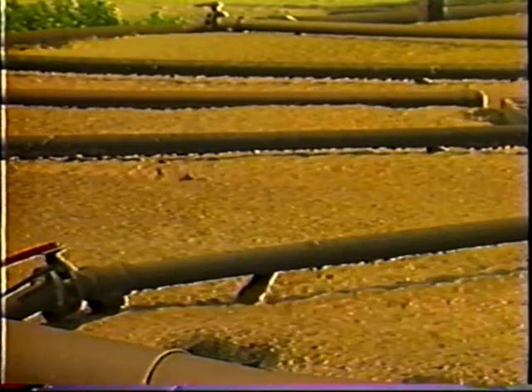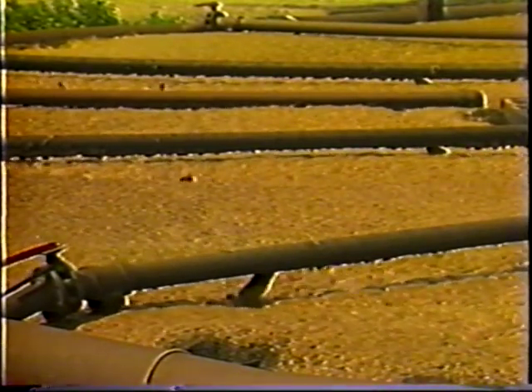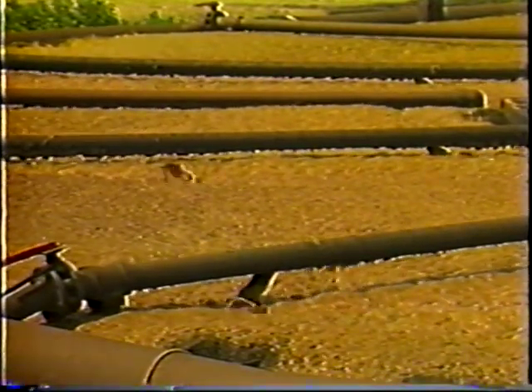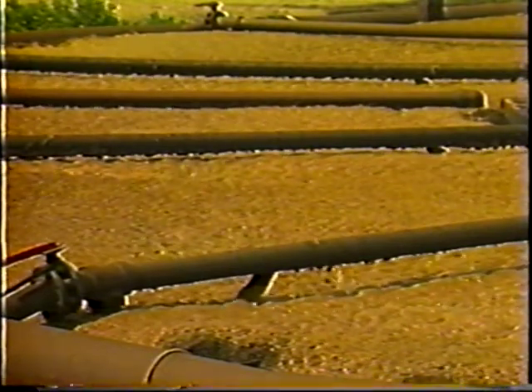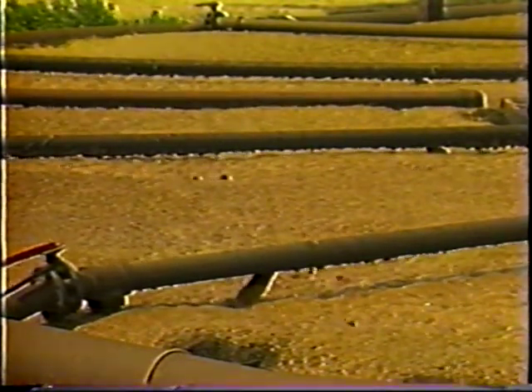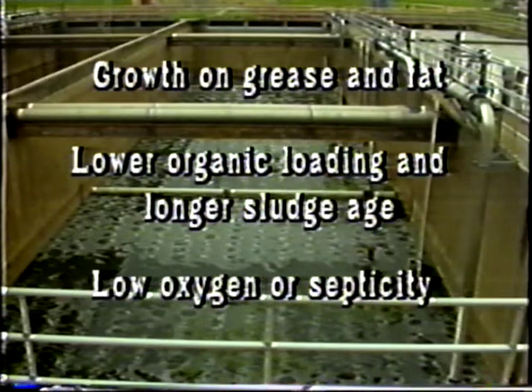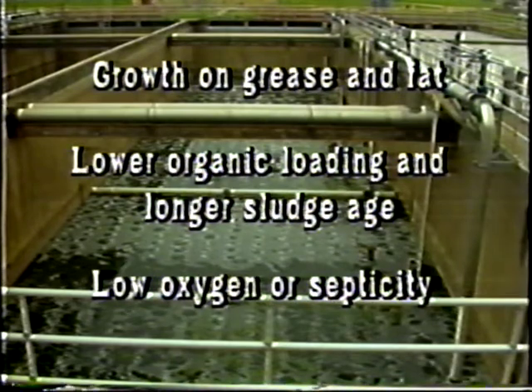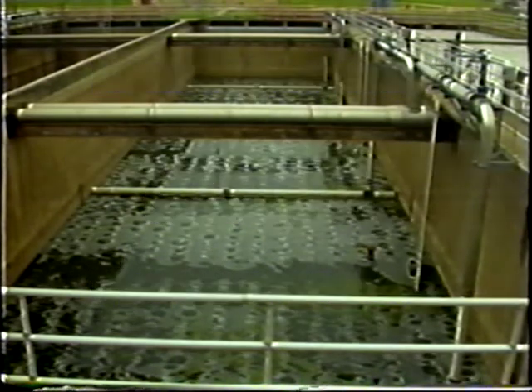Foaming is generally caused by either Nocardia or Microthrix parvicella. Both filaments have a similar cause that involves three conditions. 1. Their growth on grease and fat. 2. Lower organic loading and longer sludge age. And 3. Low oxygen or septicity.